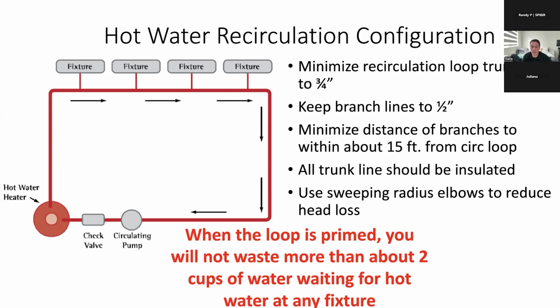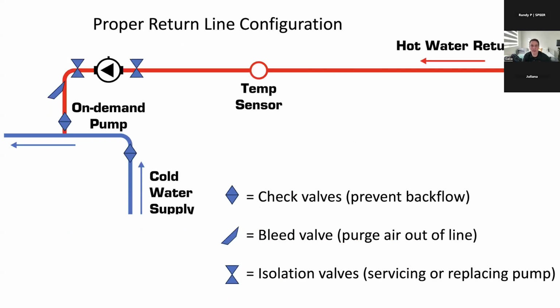So that's the goal: if we can achieve this, then you're going to have a high performing hot water distribution system. Now, to go back to the question about purging air out of the line, which is very common. Air gets into our plumbing pretty easily, either through the city, or maybe you've replaced a water heater or a plumbing fixture that required you to shut off the water to the building. In either case, it's very easy for air to get caught in the line.